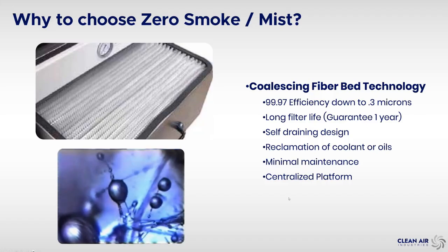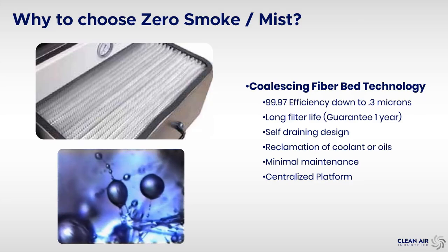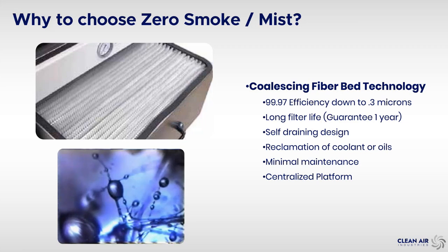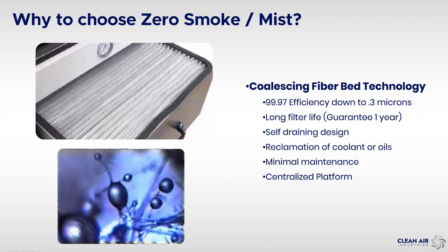But the biggest thing that I try to instill in my potential or current customers is the minimal maintenance that has to be done with these collectors. We guarantee 1 year of filter life in our collectors. And what I see mostly out in the field is it's going to be more like 2 to 3 years. Yes, the filters are fairly expensive, but compared to some of the other older technology that's out there, the payback is very, very short, because you're not maintaining these machines every single month like you do in a lot of the other ones.